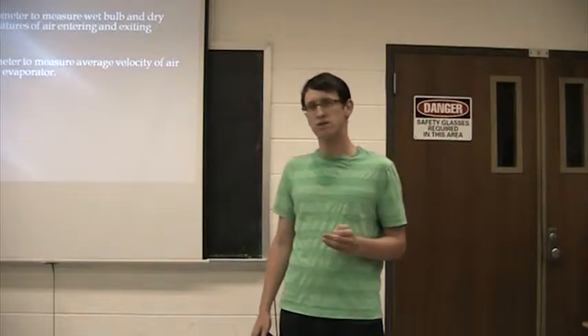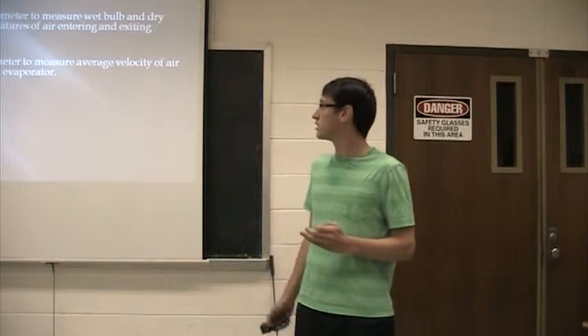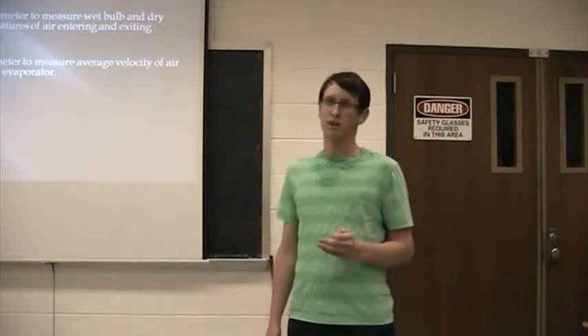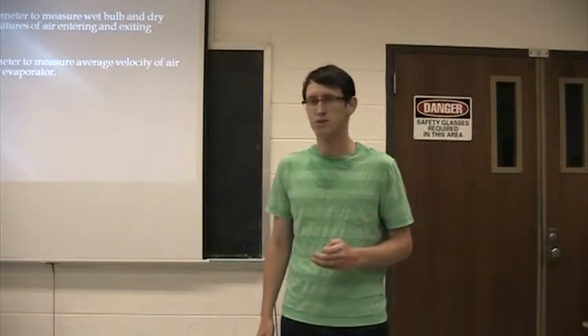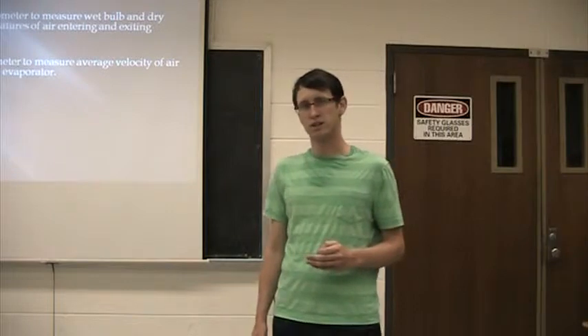Then, one group is going to use the psychrometer and the anemometer. They're going to measure the dry-bulb and wet-bulb temperatures at four points that I showed earlier. And then, also, they're going to use the anemometer to measure the velocity going in so that they can get a mass flow rate.